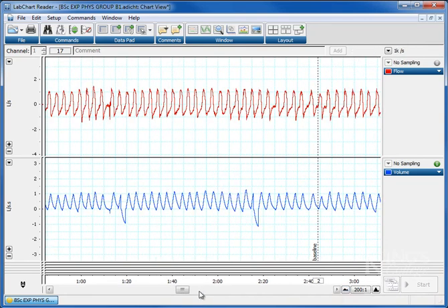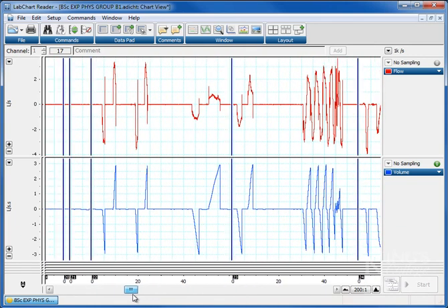However, because we were smart and we saved our calibration earlier on using the giant 3-liter syringe, we can go back in time and here are the syringe plunges recorded in the previous part of the calibration, and we knew that the volume of the syringe was 3 liters. So we're expecting these peaks to be around about 3 liters. And if I hold my mouse on the peak here, you can see it's 2.9 liters. Over here, you can see it's 2.7. Over here, you can see it's 2.9. So I'm pretty happy that we've managed to calibrate these data correctly now.